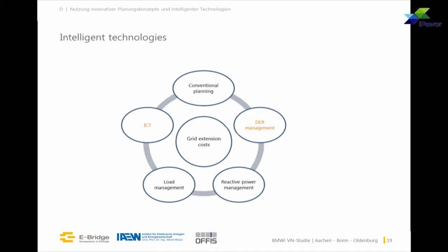We might cope with some conventional planning stuff - more number crunching, better grid documented quality data for simulations. One way would be DER management, reactive power management, load management in place, and ICT-based control technologies for the distribution grid. I'm going to focus more on the DER management and ICT part, because for planning time of German grid extension, reactive power management and load management is not of big benefit. That's for planning time of distribution grids.